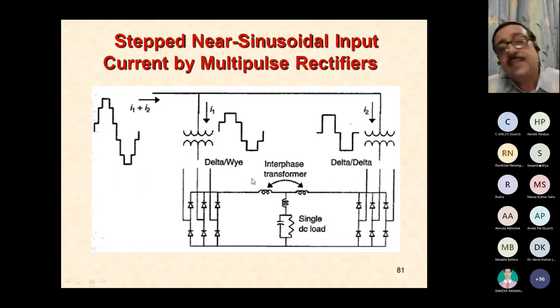Of course, one process is the multi-pulse rectifier or multi-phase rectifier, as we can say, where we have, as an example, two transformers giving a mutual 30-degree phase shift between them. Then the currents on the input sides have a 30-degree phase shift between them, and with the 30-degree phase shift, the fifth and the seventh harmonic components of current get cancelled. So therefore, you have input current which is devoid of fifth and seventh harmonic currents. It looks like a stepped waveform, and therefore you have less total harmonic distortion, so you have a better power factor on the input side. However, you need transformers, so you need a bulky component for achieving this target.